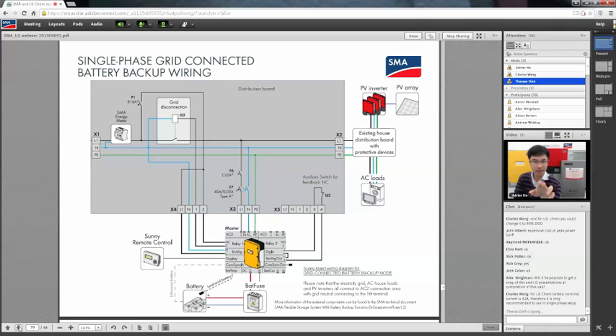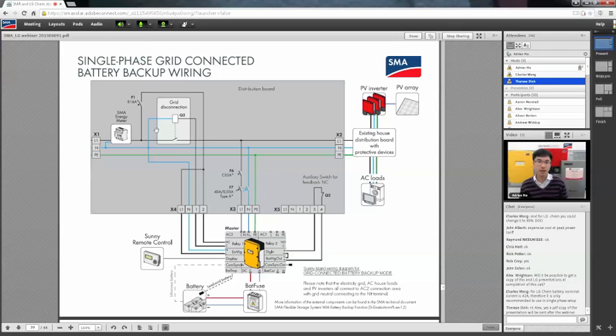You would require an AC contactor there, which I'm hovering my mouse above, Q2. Q2 is a normally open AC contactor - I've got single phase here, but you can do 3-phase of course. Q2 is a normally open contactor with an auxiliary switch, which is in a different position - normally closed. So the contactor itself is normally open, and the auxiliary switch on the right-hand side is normally closed.